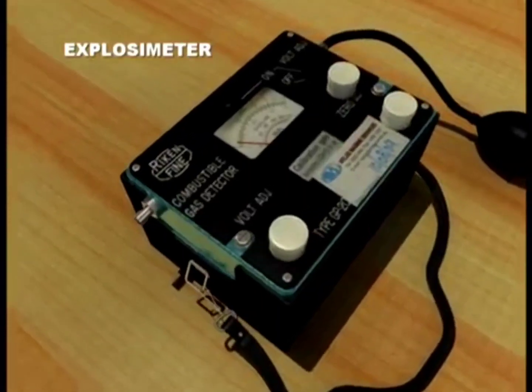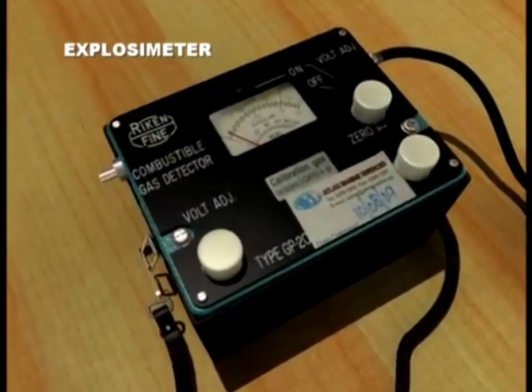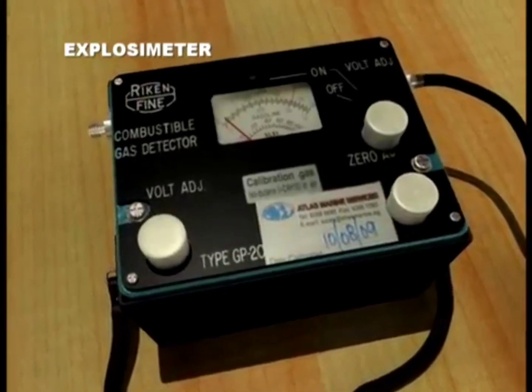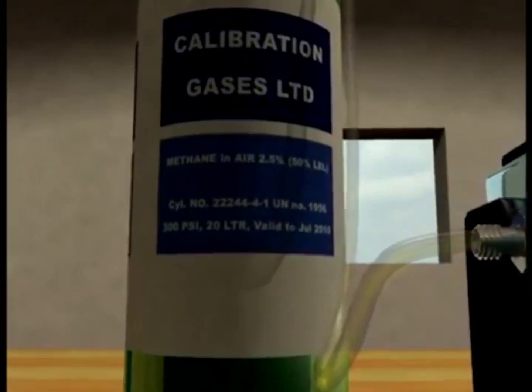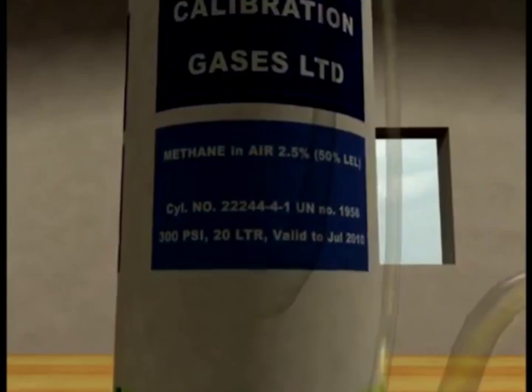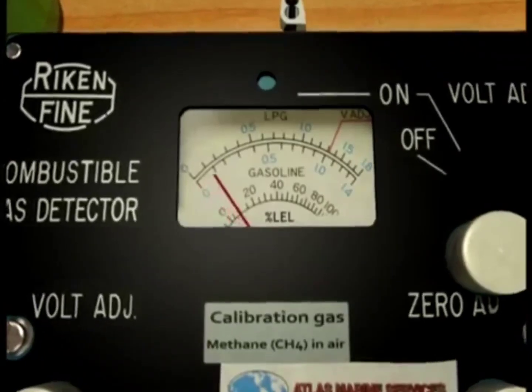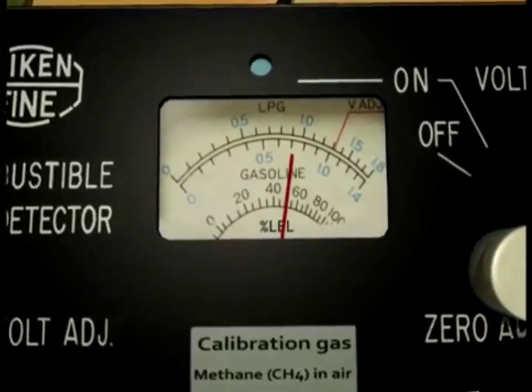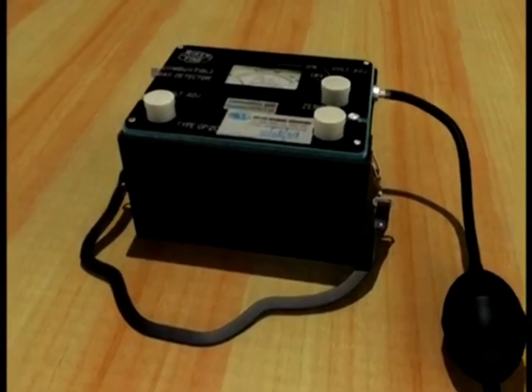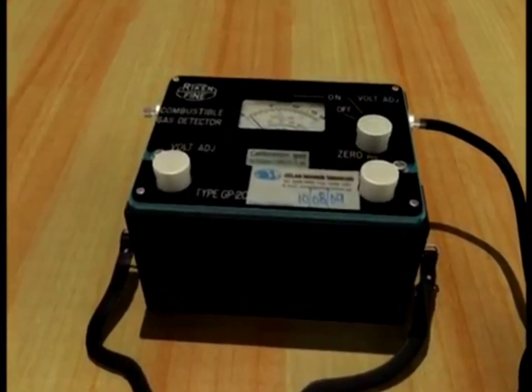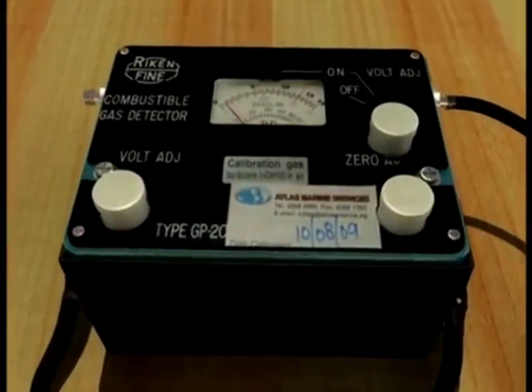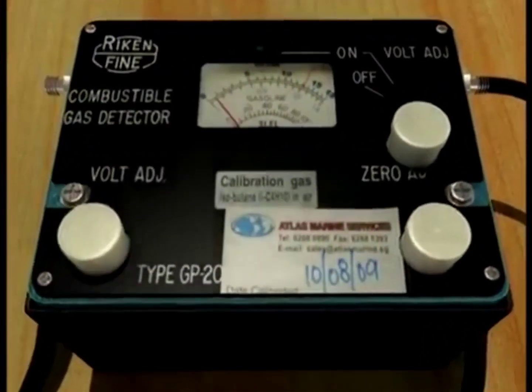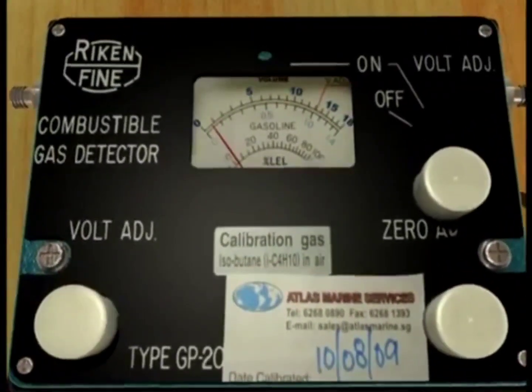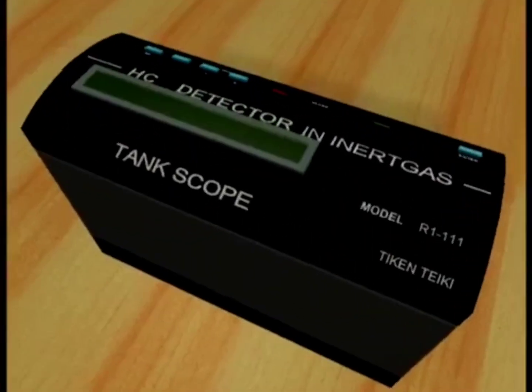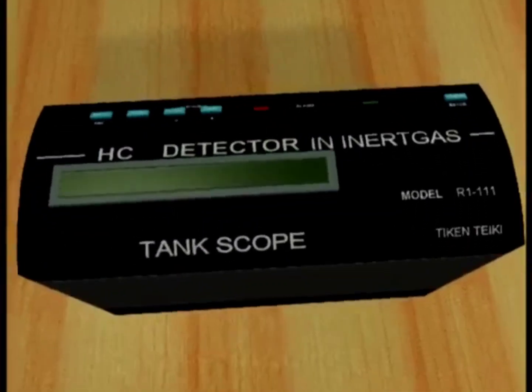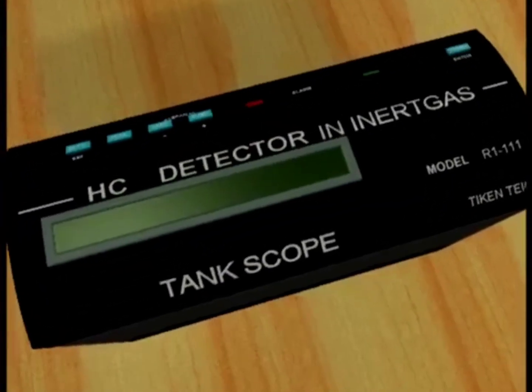Portable explosimeter is used to detect the percentage of combustible gas present in a non-inert atmosphere, that is, in air. The reading is expressed in percentage of the lower explosive limit of hydrocarbon gas. Portable combustible gas detector, which gives reading in units of percentage volume of hydrocarbon gas in air. This may be combined with an explosimeter. Tank scope, which gives reading of hydrocarbon gas as percentage volume in an inert atmosphere.